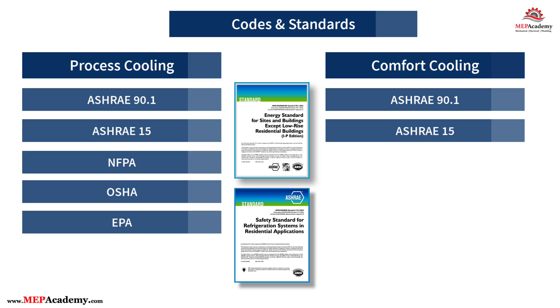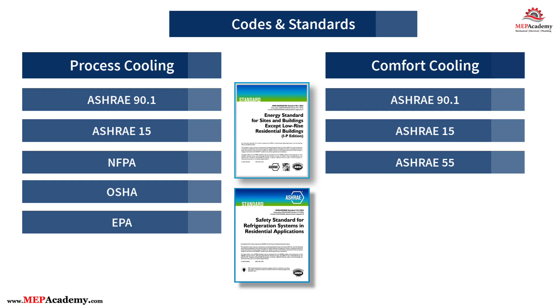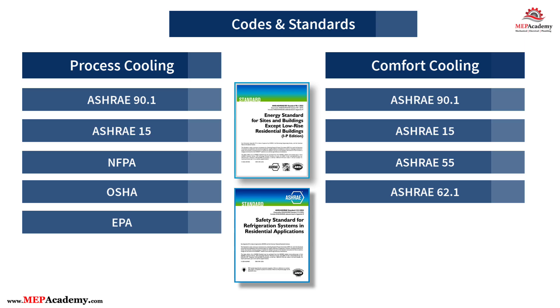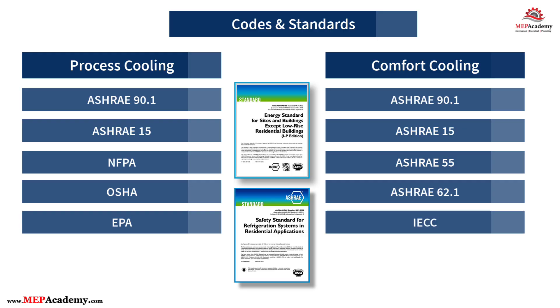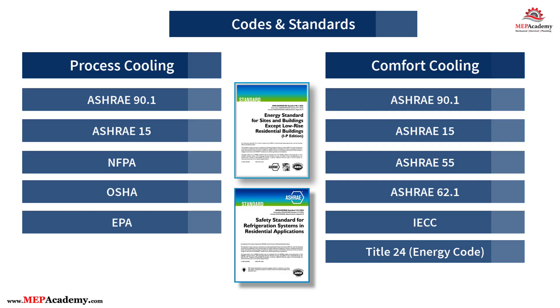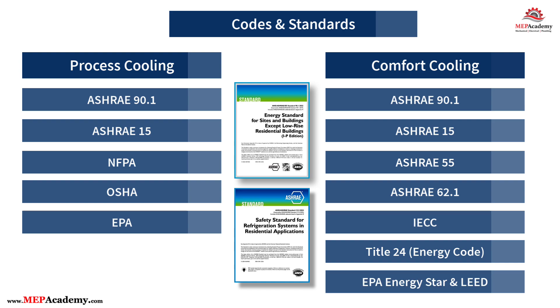Comfort cooling standards include ASHRAE 55, thermal environmental conditions for human occupancy, which specifies acceptable thermal conditions for human comfort; ASHRAE 62.1, ventilation for acceptable indoor air quality; IECC (International Energy Conservation Code), which establishes energy efficiency requirements for HVAC systems and buildings; Title 24 California Energy Code, which mandates efficiency standards for air conditioning and comfort cooling; and EPA Energy Star and LEED (Leadership in Energy and Environmental Design), which encourage high-efficiency comfort cooling systems.